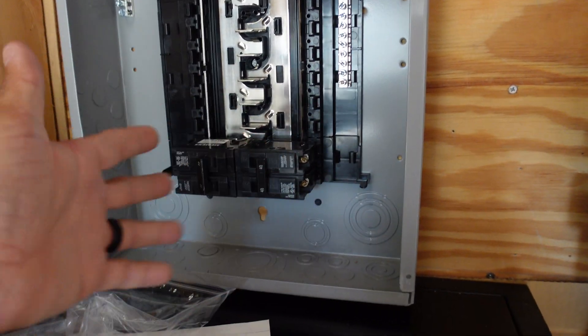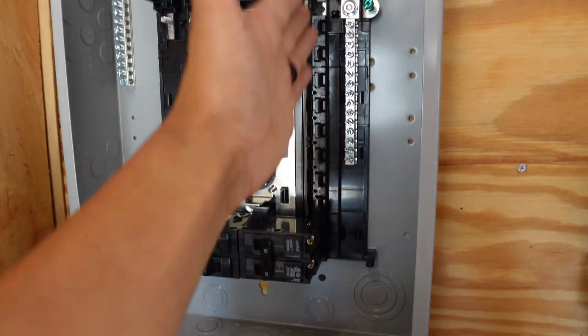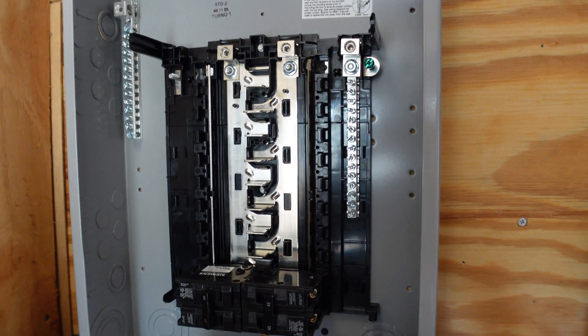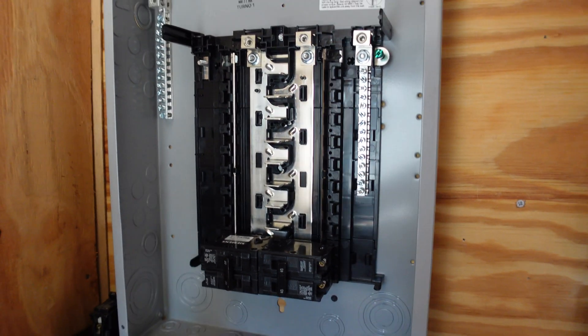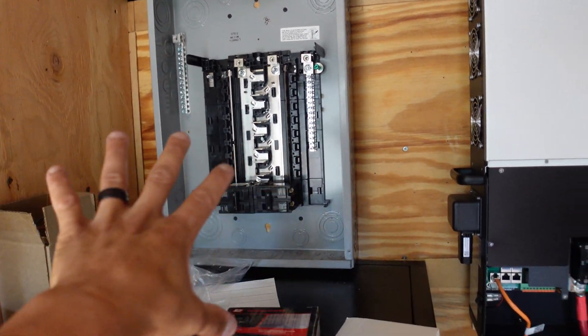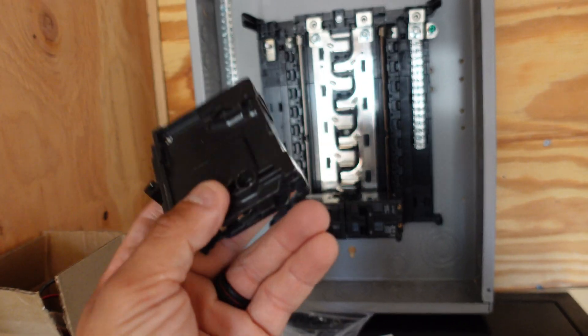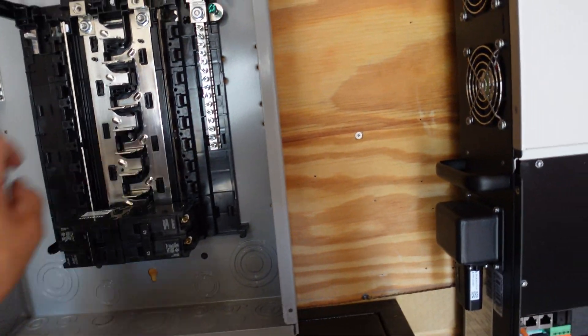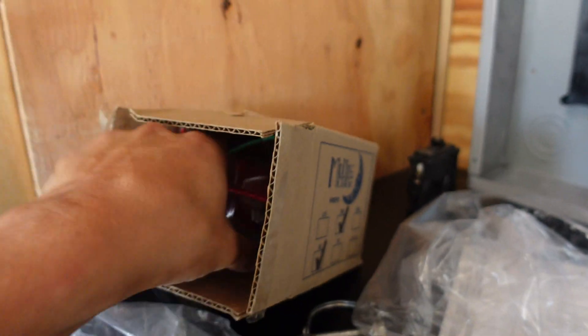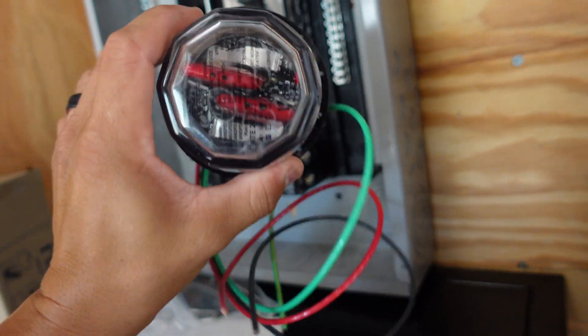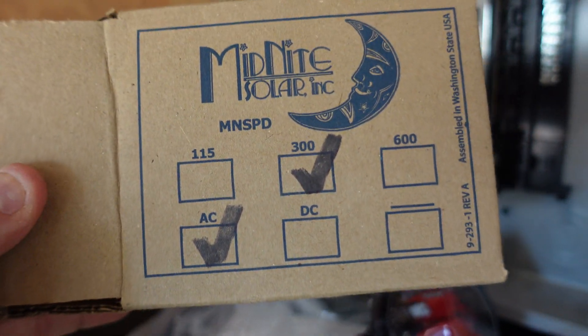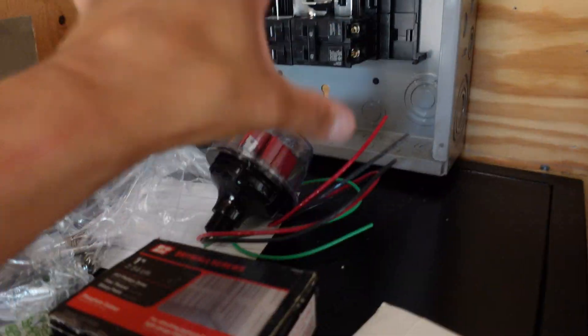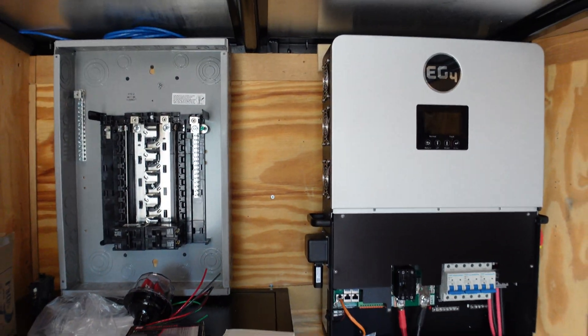So again, 40 amps is gonna be on this side. I could add literally up to five on this side and five on this side. That's way more than enough, I don't think I'm ever gonna go more than two, possibly three max. And then I have a 20 amp breaker right here that we're gonna be saving for a later date just in case I need like a 120 outlet somewhere. I do actually have to wire this guy as well. This is a surge protector for AC side, as you can see this came with my Signature Solar kit. This should be good for surge protection on this panel. Let me get this cut up, let me wire this up and I'll show you guys what it looks like in a second.